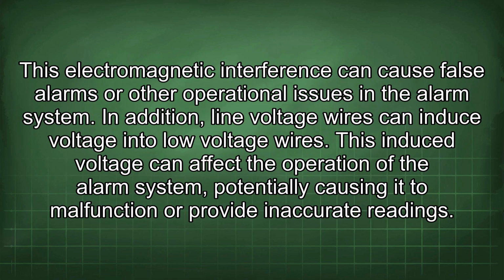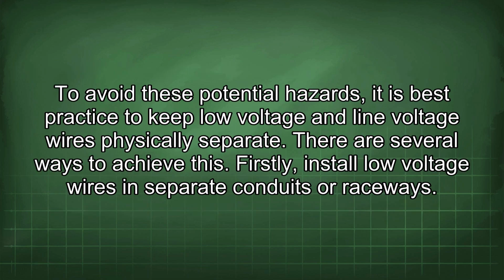This electromagnetic interference can cause false alarms or other operational issues in the alarm system. In addition, line-voltage wires can induce voltage into low-voltage wires. This induced voltage can affect the operation of the alarm system, potentially causing it to malfunction or provide inaccurate readings. To avoid these potential hazards, it is best practice to keep low voltage and line voltage wires physically separate.